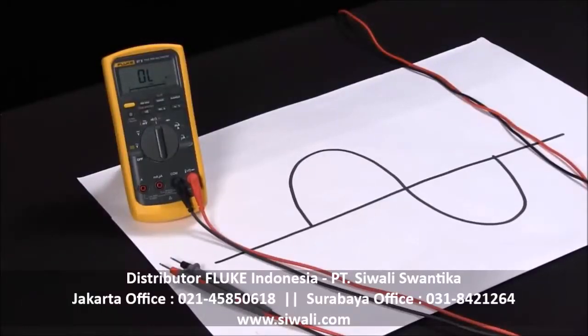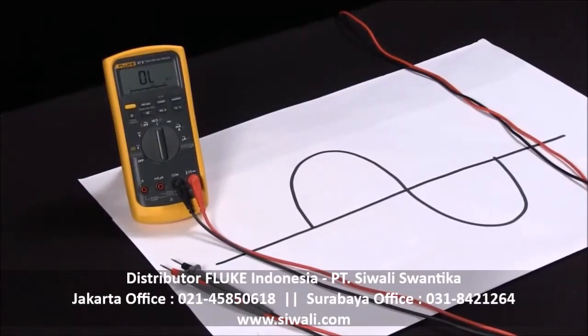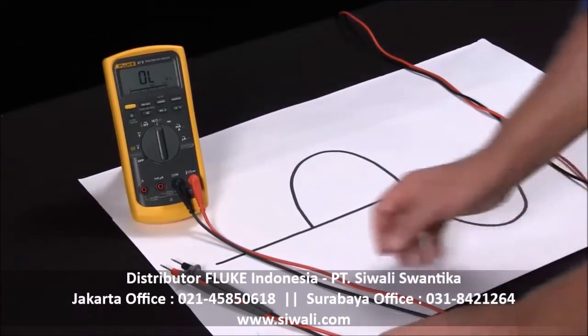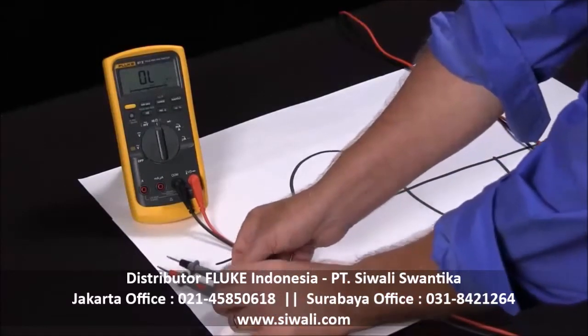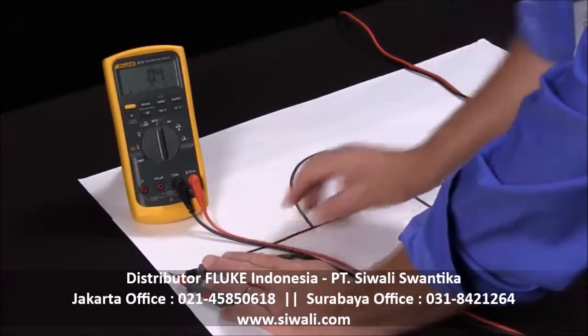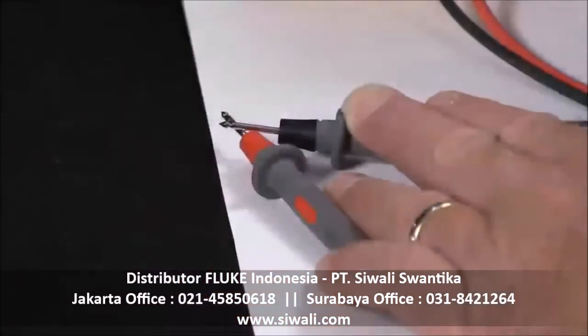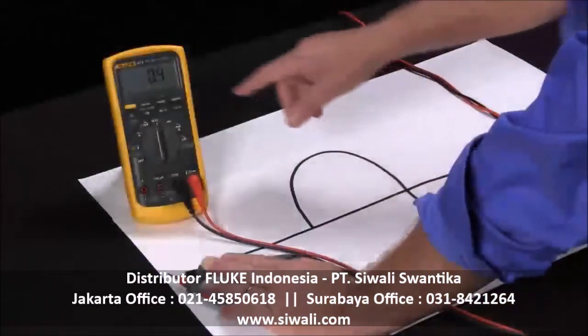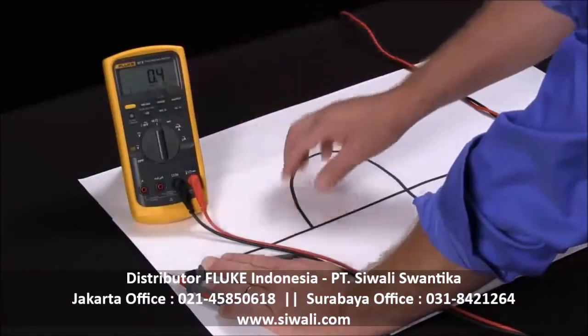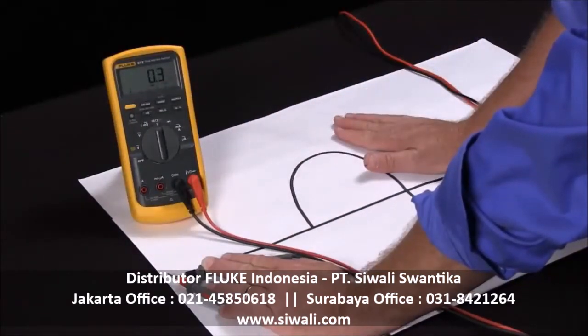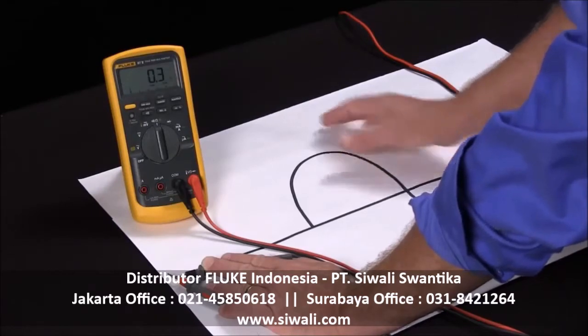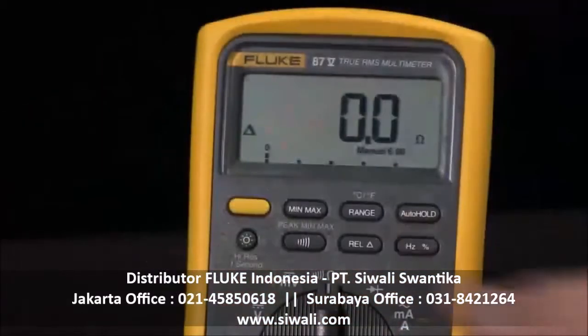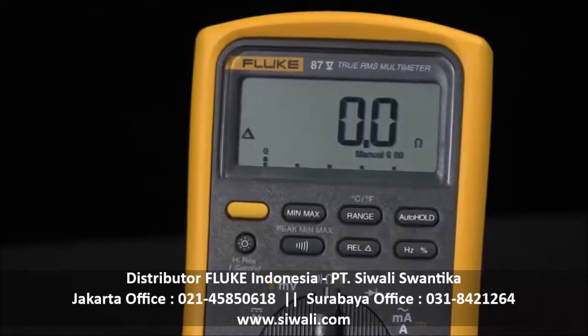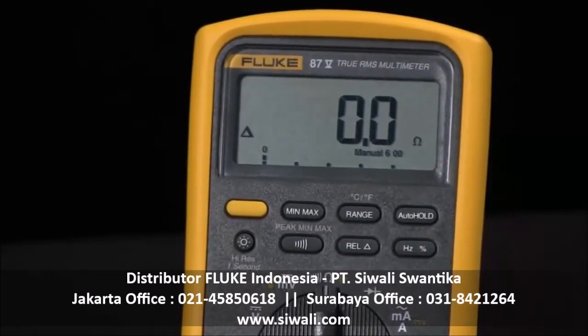We're here to explain the delta or relative function that you'll find on meters, and we're using the Fluke 87 V as the example. One of the main reasons for the delta or relative mode is when I have a set of lead resistance on test leads. Any set of leads is going to have a certain amount of resistance, so I have 0.4 ohms in these leads. If I want to measure something accurately, I either have to mentally subtract that, or if I hit the relative mode, it takes that reading and makes it 0. So now everything I measure will have that subtracted out of it, and I'll get a more true reading.